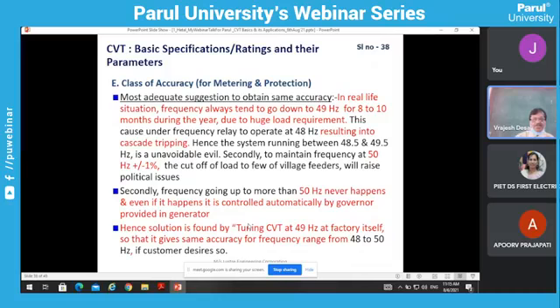So the CVT becomes a very sensitive element in the power system. But as per the rule of the CEA committee, the frequency has to be maintained by controlling the governor of the generator, so it is possible. But when I was in ABB, I checked that if you tune the CVT to 49 hertz instead of 50 hertz, which is normally prevailing in the system, then the CVT can meet all the VA burdens mentioned in the previous slide, from 48 to 50 hertz.